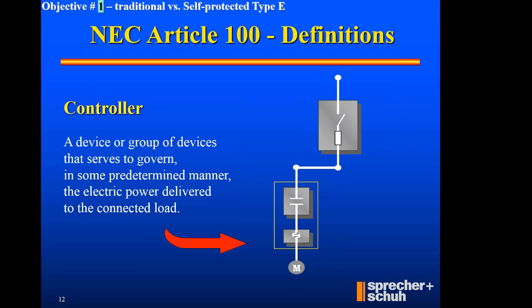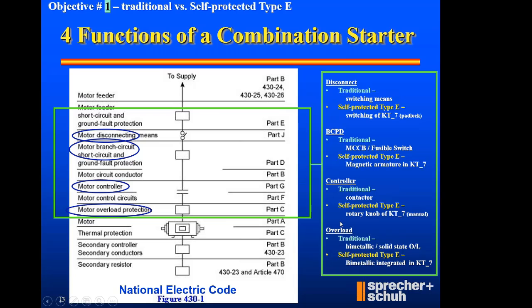Getting past the upstream disconnect and protection portion, now I'm moving down into the controller portion. The controller, okay, I've got a motor starter circled here. The controller is the contactor with the open contact here. And the overload protection, National Electrical Code says every load needs an overload, so there's your overload, just to complete the basic concept of a circuit. Now that I've identified the basic concept, let's apply how we can say self-protected type E does the job for us.